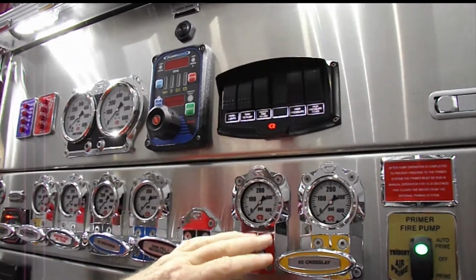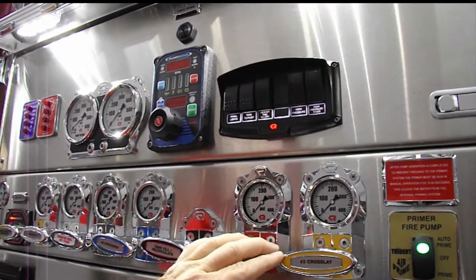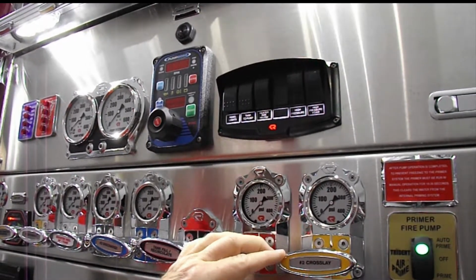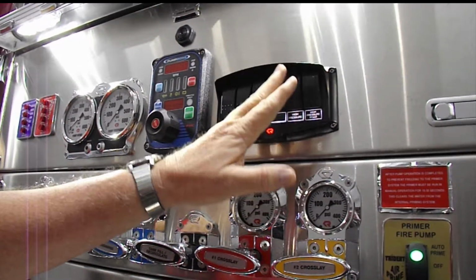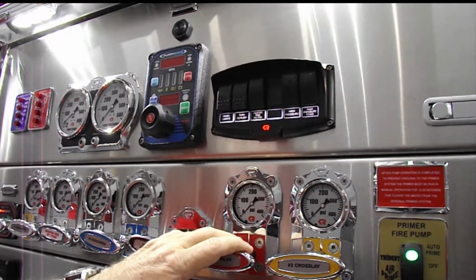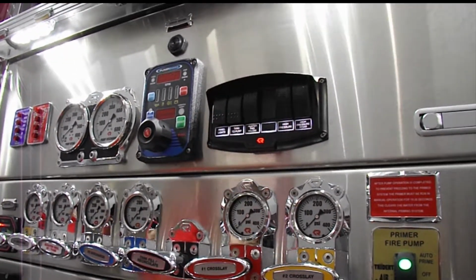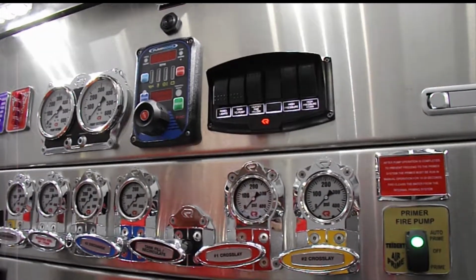When you kick that in, then we open a valve that sends fire water into those other impellers. And that's when you get your high pressure. And then high pressure foam, because it's only on and off on these systems, you either get it or you don't. It's a set, there's no setting to adjust that. It's either on or off.